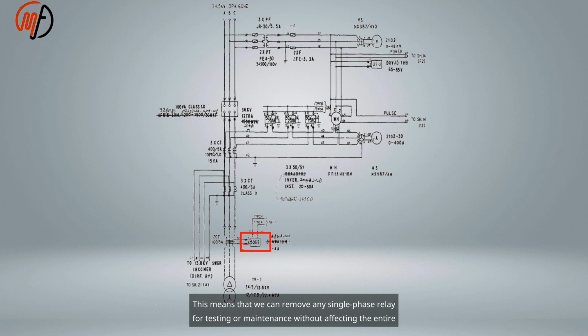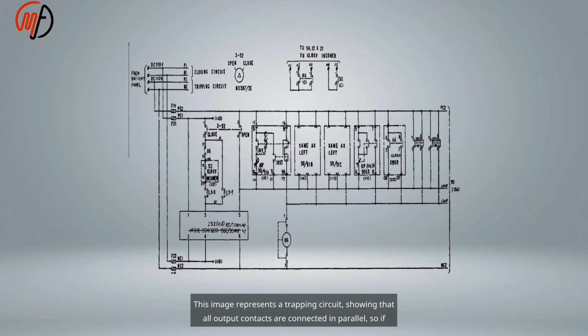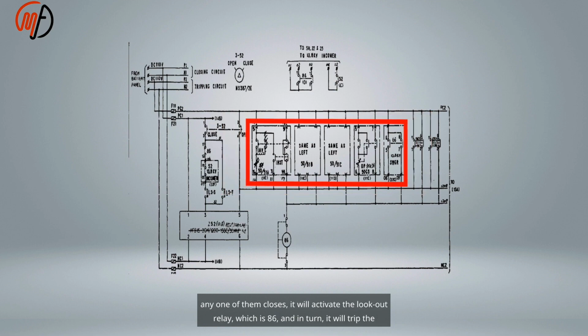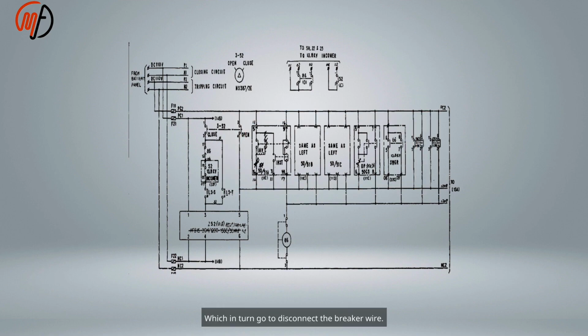This means that we can remove any single-phase relay for testing or maintenance without affecting the entire protection system. This image represents a tripping circuit showing that all output contacts are connected in parallel. So, if any one of them closes, it will activate the lockout relay, which is 86, and in turn, it will trip the circuit breaker, which in turn will disconnect the breaker wire.